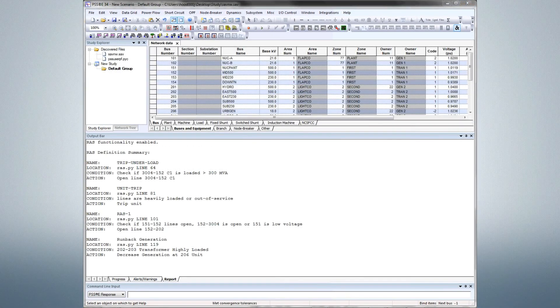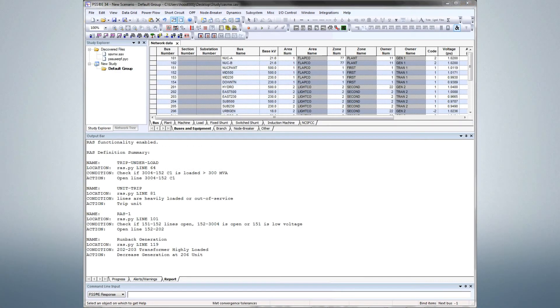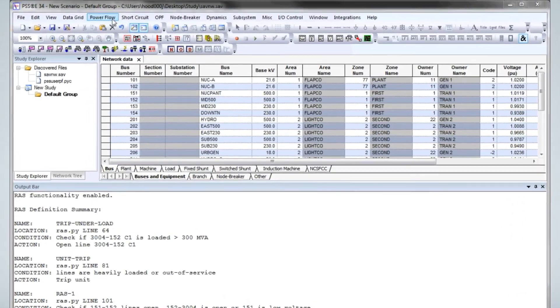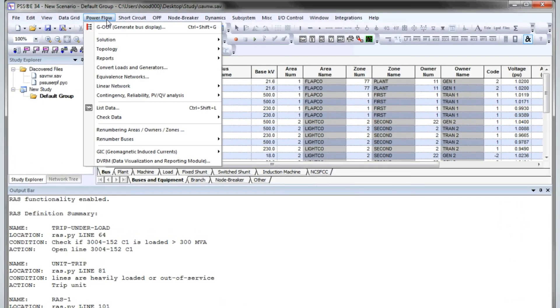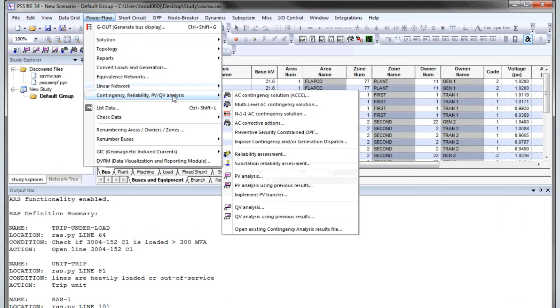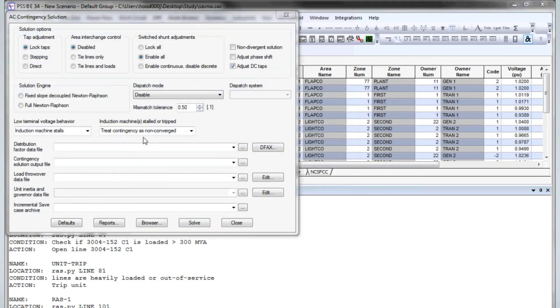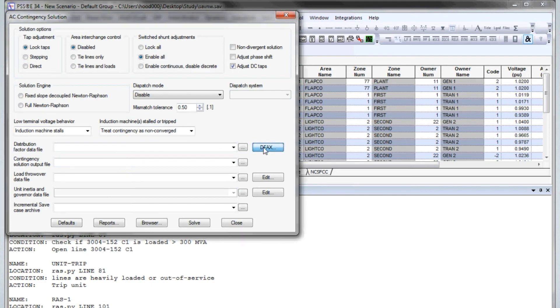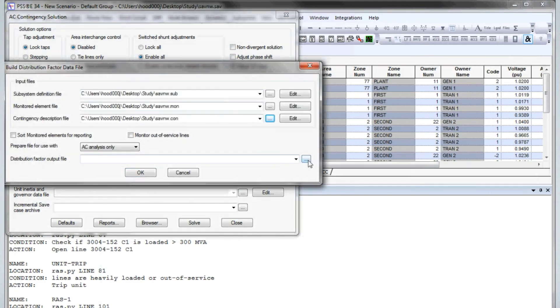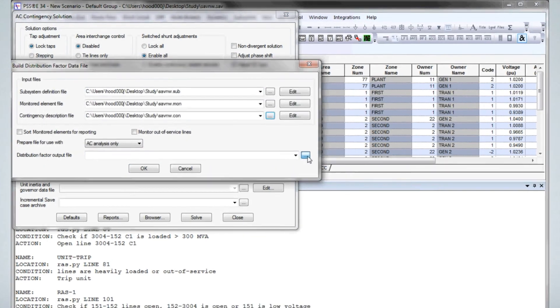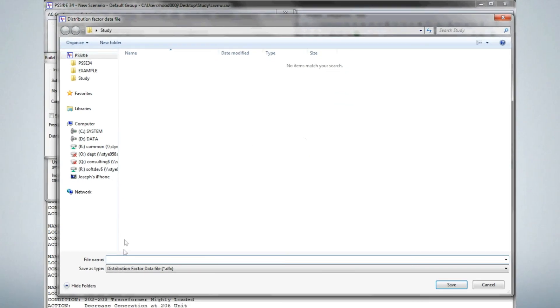Let's run contingency analysis with these RAS definitions. Click Power Flow, Contingency, Reliability, PVQV Analysis, AC Contingency Solution. Click the DFAX button and load the sub, mon, and con files. Then save the DFAX as savnw.dfx.